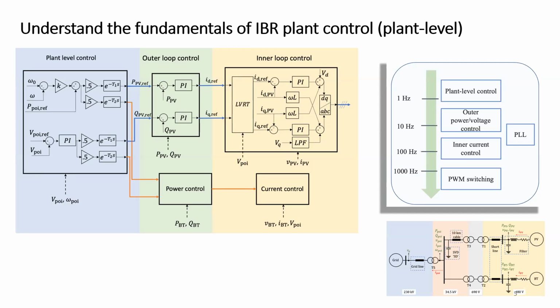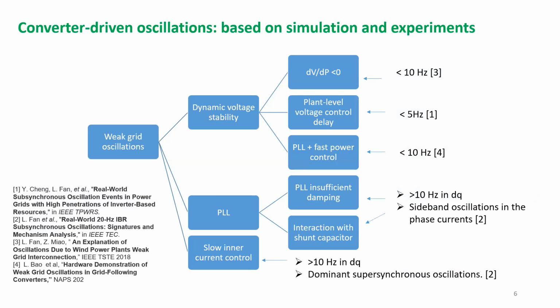Combining all together, the fundamental we need to understand is this bandwidth difference. For example, if we see dynamics at 1000 Hertz, it is probably PWM switching combined with the filter or other hardware. At the 100 Hertz level, you can guess it is probably an inner current control related issue. At 10 Hertz and above, you can guess it's probably the PLL or outer power or voltage control. And at very low frequency, it is probably plant level control. So that's what's happening in the fundamentals.